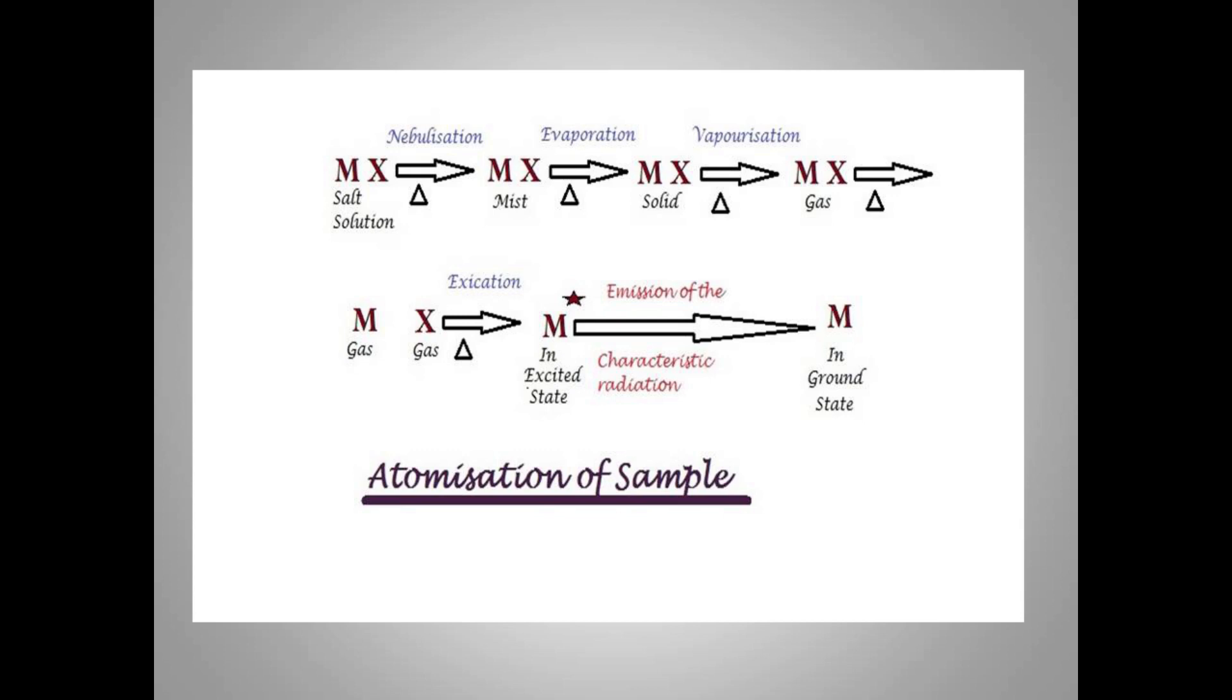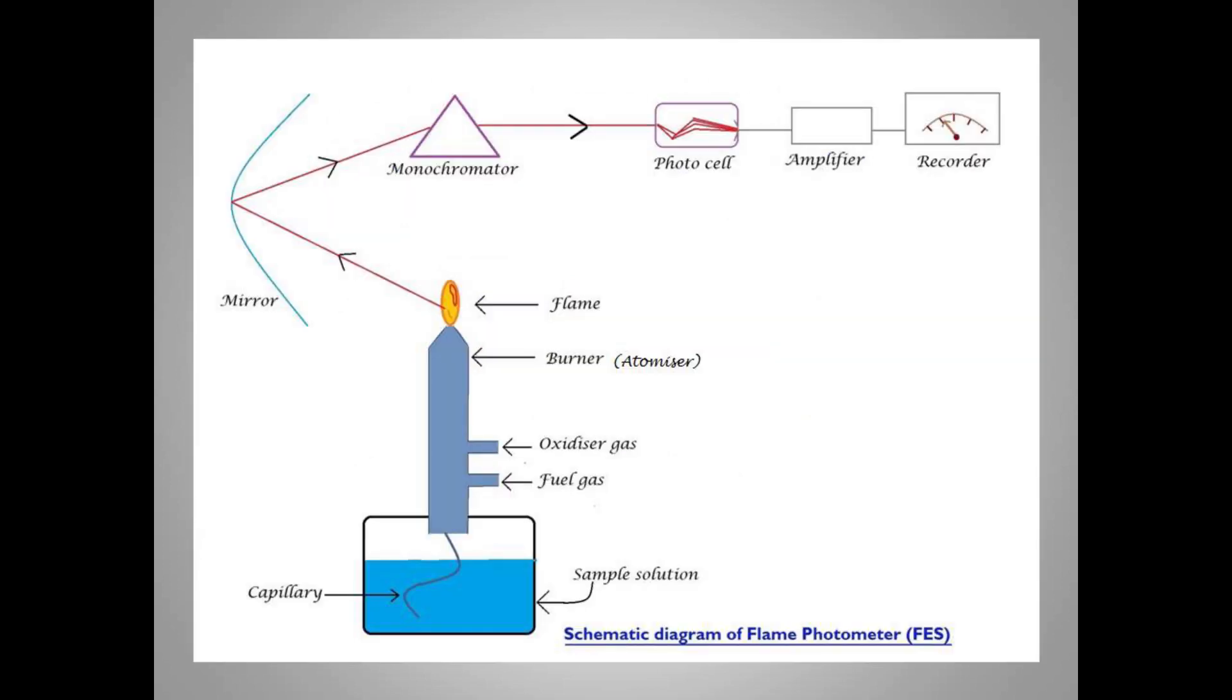This is the schematic diagram of flame photometer, which works on the principle of flame emission spectroscopy. Seen in the diagram is the burner, which is the important component of the flame photometer. The burner is attached to the sample solution. The sample solution reaches to the flame and then the further steps take place. The other components which can be seen are the mirror, the monochromator, the photocell, amplifier, and recorder.